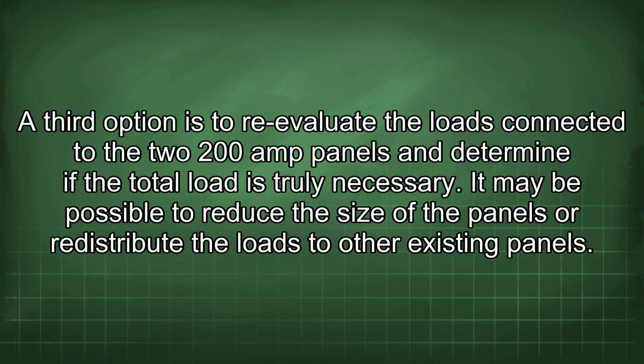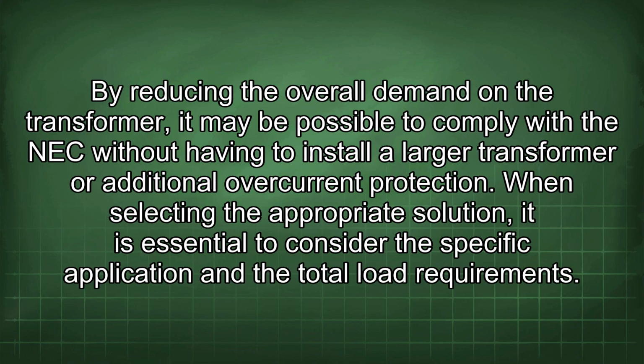A third option is to re-evaluate the loads connected to the two 200-amp panels and determine if the total load is truly necessary. It may be possible to reduce the size of the panels or redistribute the loads to other existing panels. While reducing the overall demand on the transformer, it may be possible to comply with the NEC without having to install a larger transformer or additional overcurrent protection.